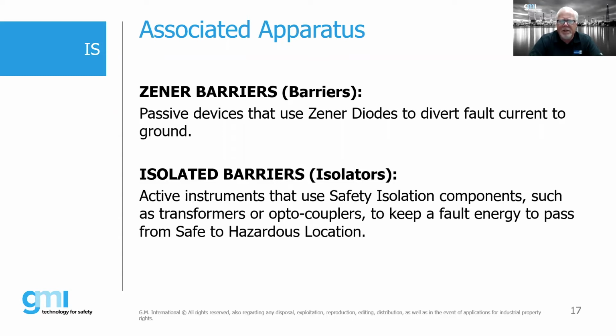So the difference is that isolated barriers use safety isolation components, generally transformers or optocouplers, to keep fault energy from passing from a safe to a hazardous area. So Zener barriers are typically a passive device, a fairly simple device. An isolated barrier uses a little bit more components, and we'll show that here in some of these additional slides.